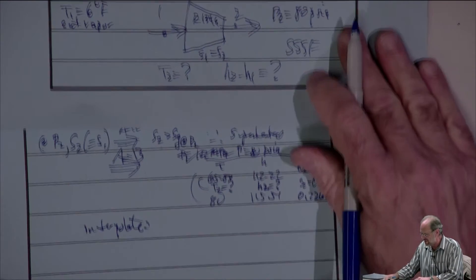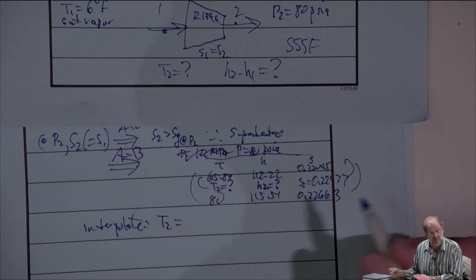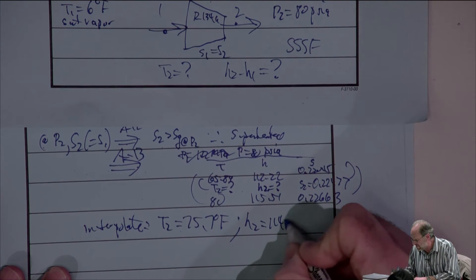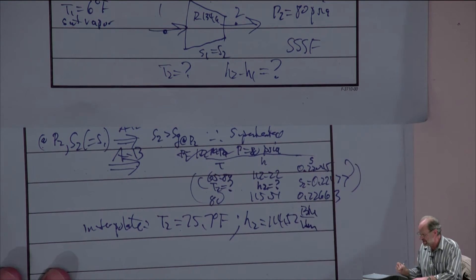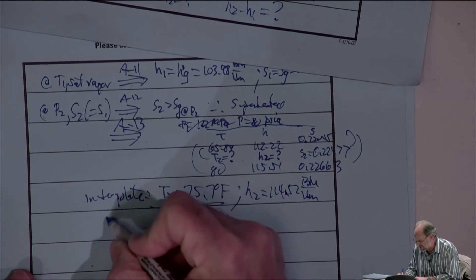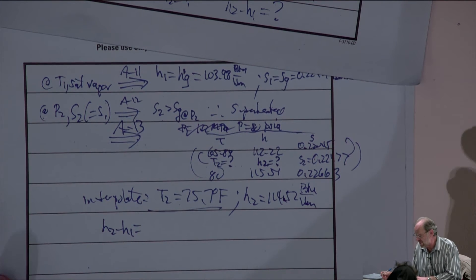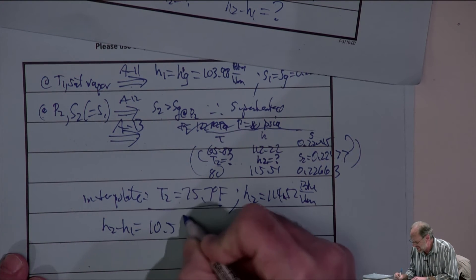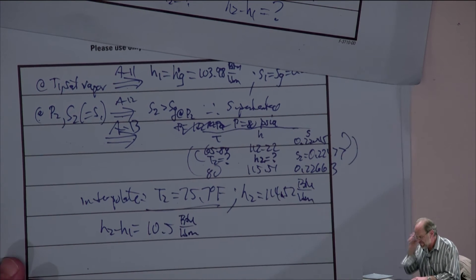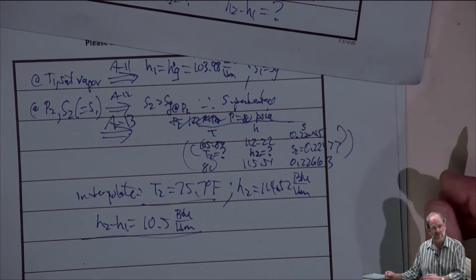Doing the interpolation, T2 is 75.7 degrees Fahrenheit and H2 is 114.52 BTUs per pound mass. The enthalpy change H2 minus H1 is approximately 10.5 BTUs per pound mass (more precisely 10.54). That's Part A completed — the discharge temperature and enthalpy change.